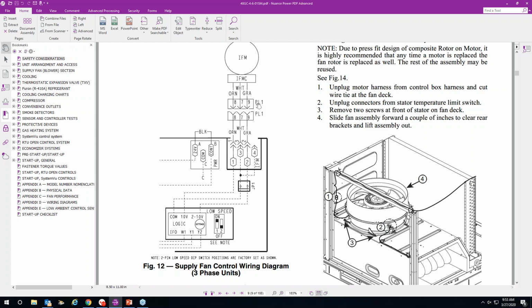Then you're going to have this connection, harness connector, that's going to be in the blower compartment, which is right here. Okay, so here's our control box over here. I'm going to go into the blower cabinet, and I'm going to look at this harness. Do I have my signal voltage here? If I do, and it's going back to the motor, and that motor is not running, it may be locked up from what we were just talking about earlier, or it may have failed. Something may have failed on it.